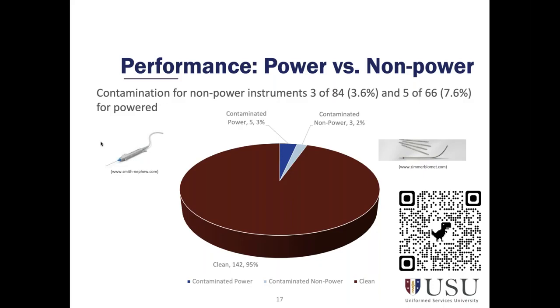I found out that there were issues with the system. They were not using the right brushes. If you don't know about the Smith & Nephew shaver, it requires 3 different brushes to clean this piece of equipment. They didn't have any of them. They were trying to clean it with a standard brush that did not do the job.